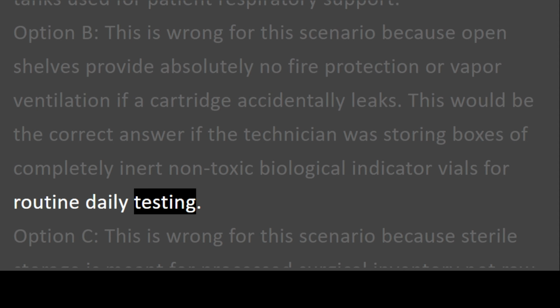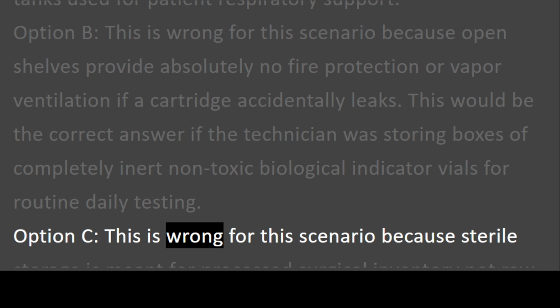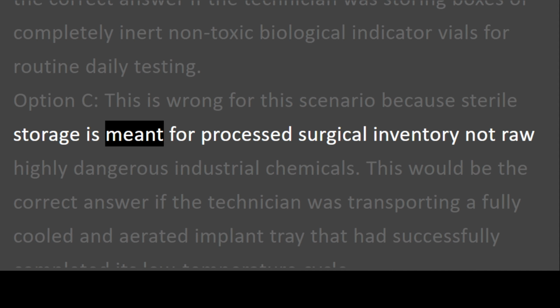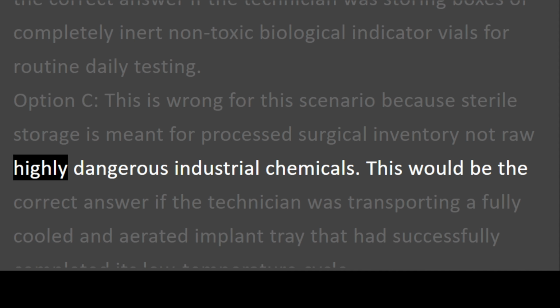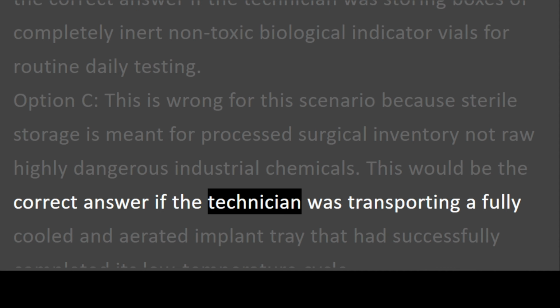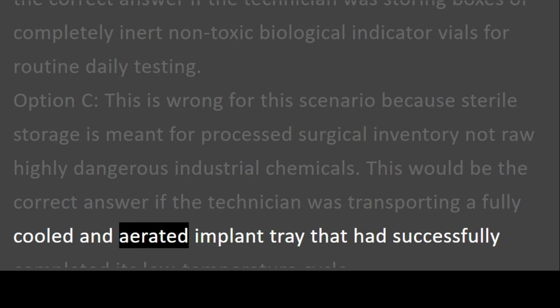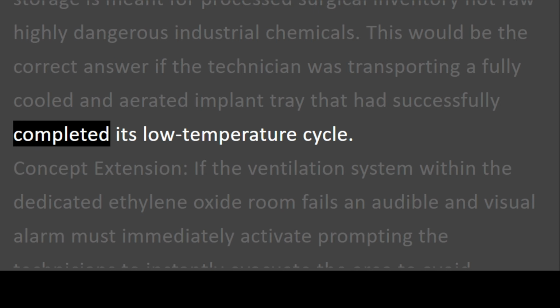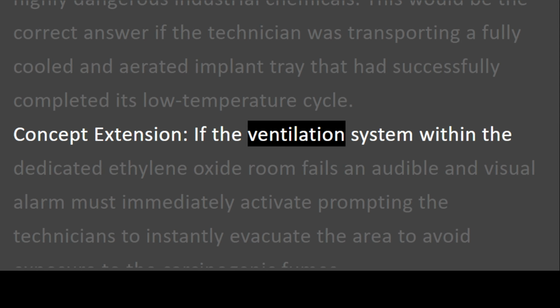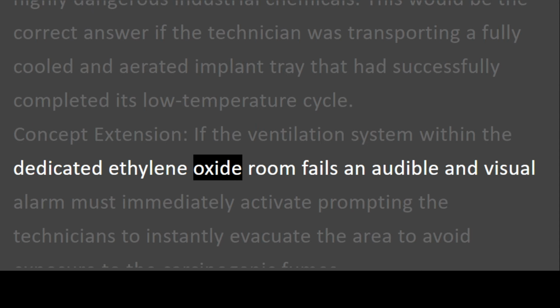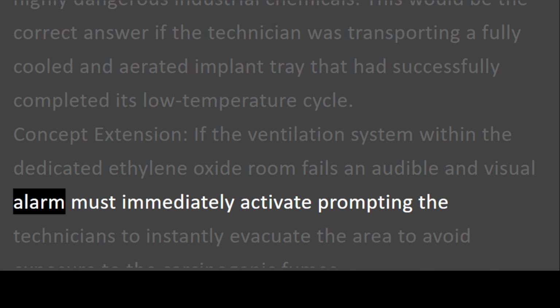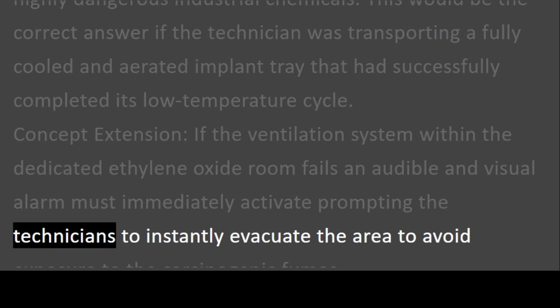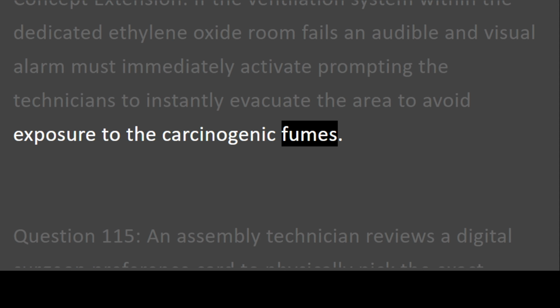Option C. This is wrong for this scenario because sterile storage is meant for processed surgical inventory, not raw, highly dangerous industrial chemicals. This would be the correct answer if the technician was transporting a fully cooled and aerated implant tray that had successfully completed its low-temperature cycle. Concept extension. If the ventilation system within the dedicated ethylene oxide room fails, an audible and visual alarm must immediately activate, prompting the technicians to instantly evacuate the area to avoid exposure to the carcinogenic fumes.